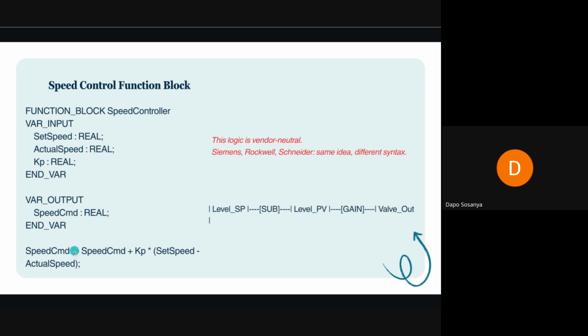This shape here, this symbol shows that you are acting on the existing speed command. So whatever you have here, you are adding it to this speed command, whether you add or subtract from it. The set speed is your set point, and the actual speed is the one you measured. Look at these brackets: set speed minus actual speed. You multiply it by this KP, a factor, and then add that to your existing speed command. So at the end of the day, you begin to realize that control is actually understanding.